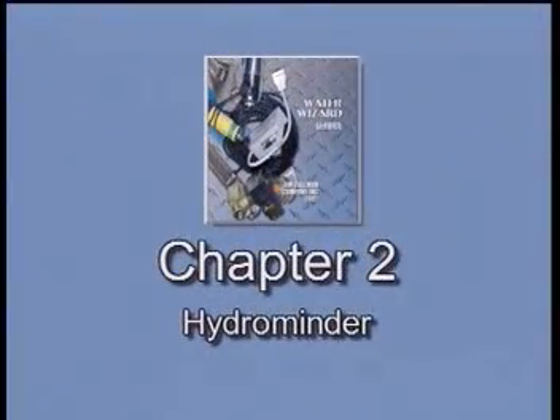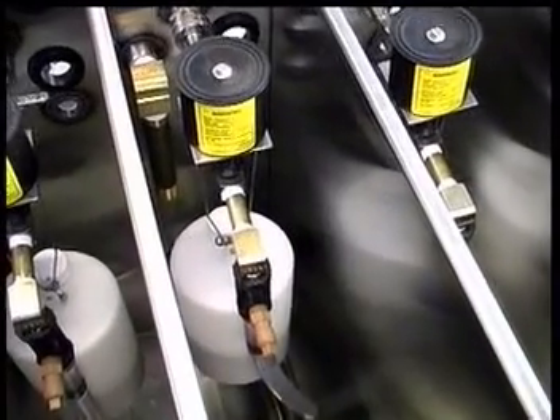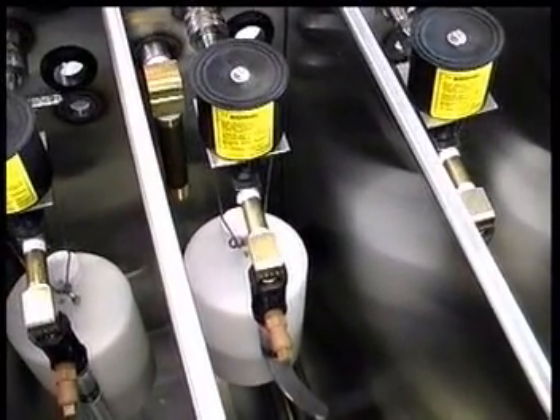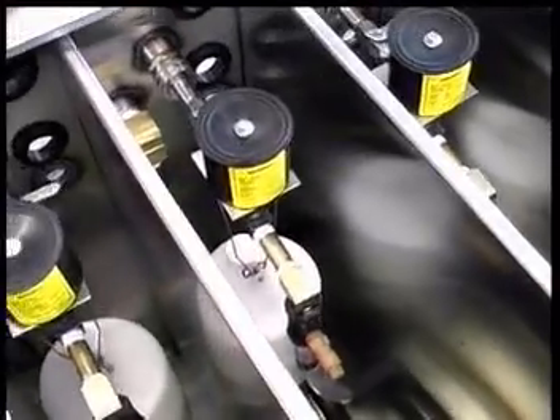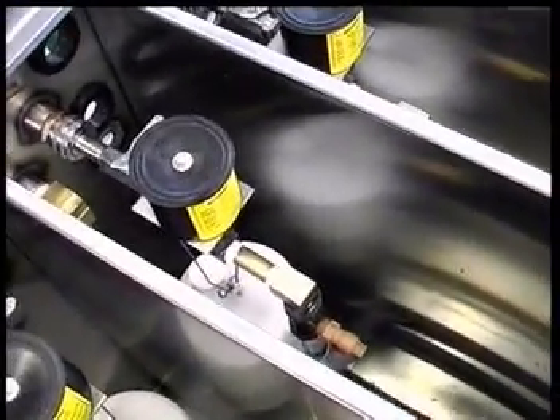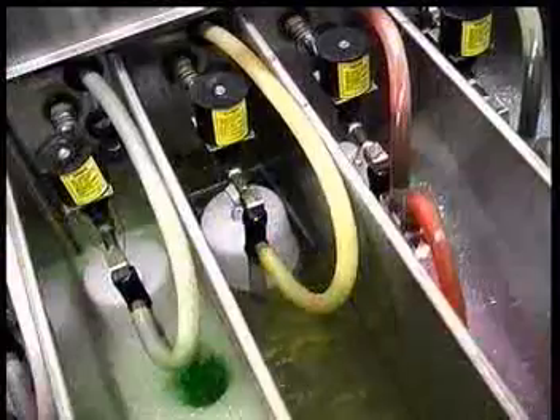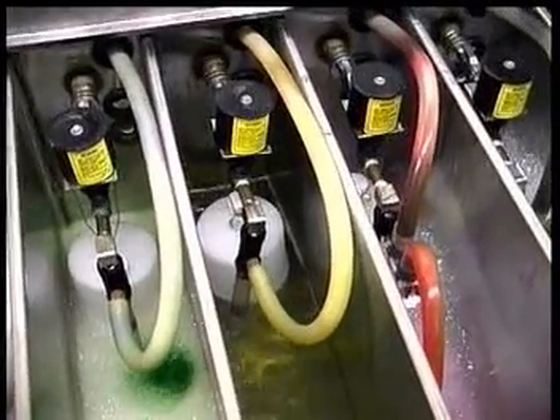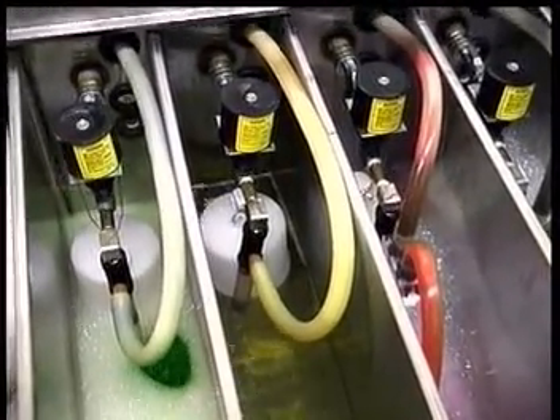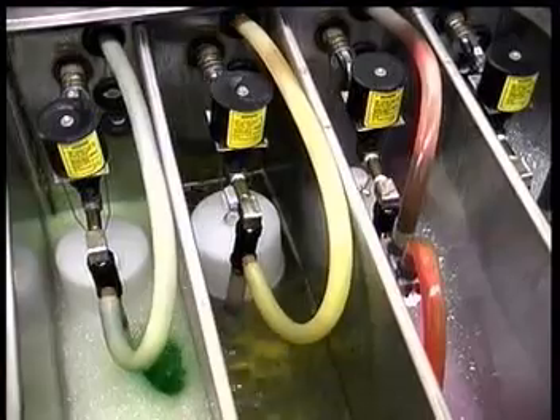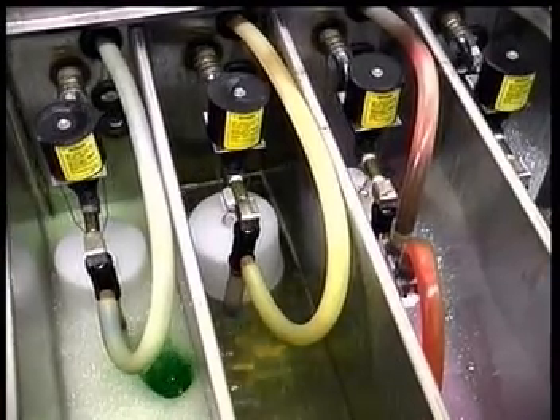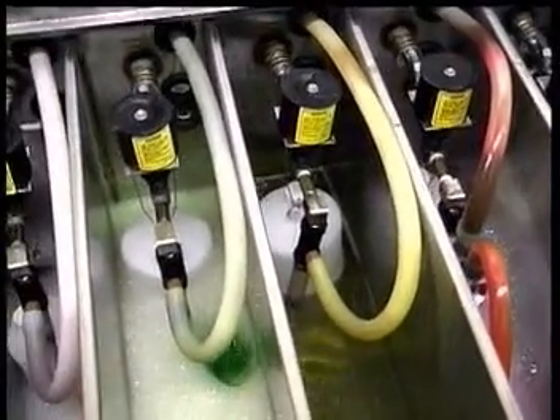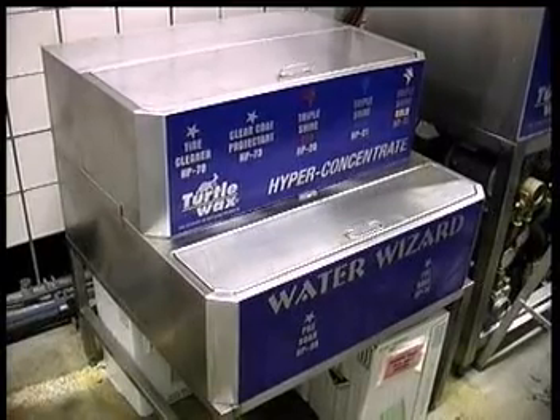The Hydrominder is an automatic mixing valve operated by a float control and constant water pressure of 40 to 60 psi. When the float drops low enough to open the valve, water flows through the diaphragm, then through the eductor. As water flows past the eductor, it creates a venturi that draws chemical from the storage tank through the siphon hose.